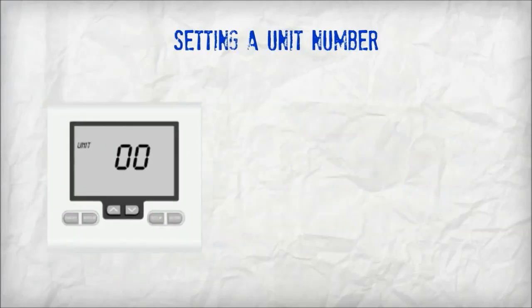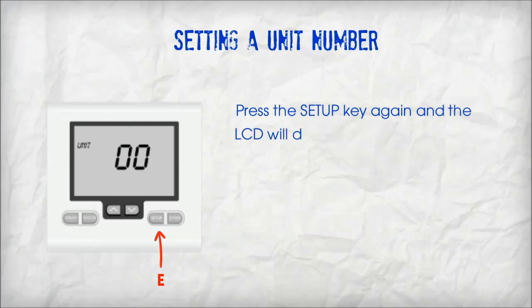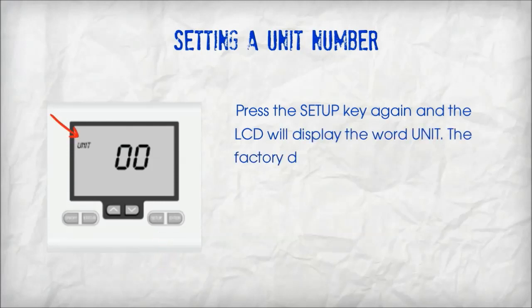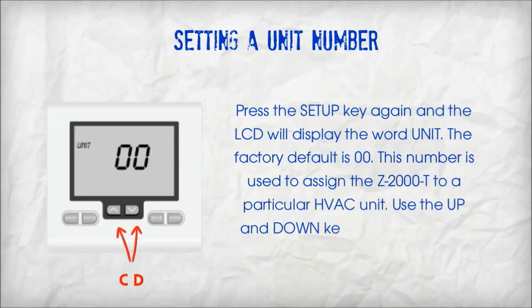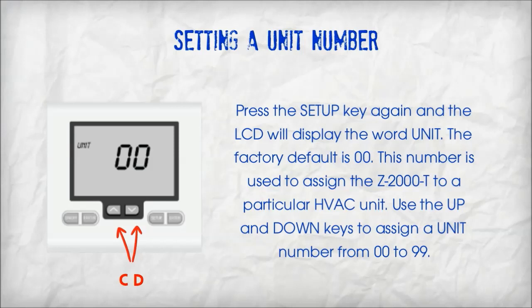Setting a unit number. Press the setup key again and the LCD will display the word 'unit'. The factory default is 00. This number is used to assign the Z2000T to a particular HVAC unit. Use the up and down keys to assign a unit number from 00 to 99.